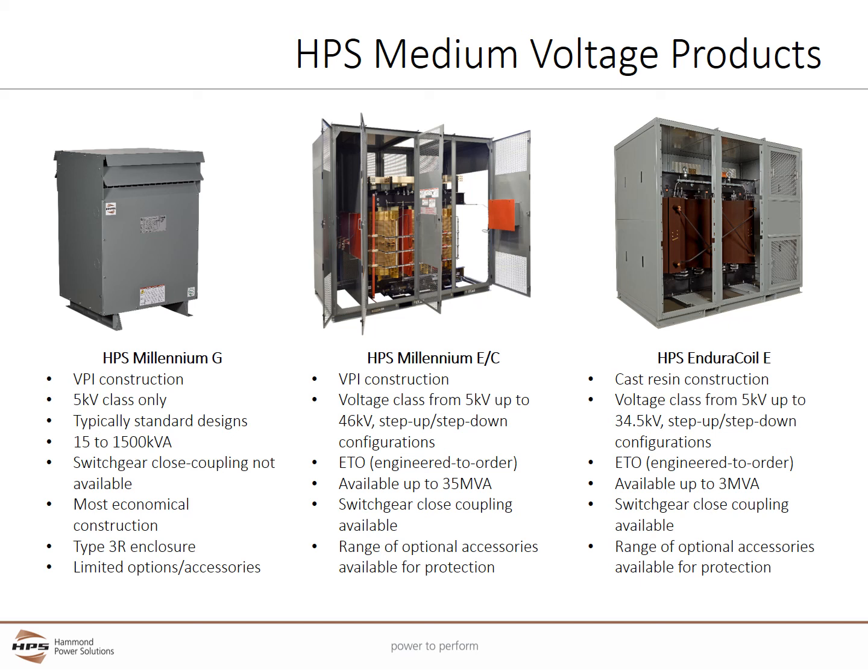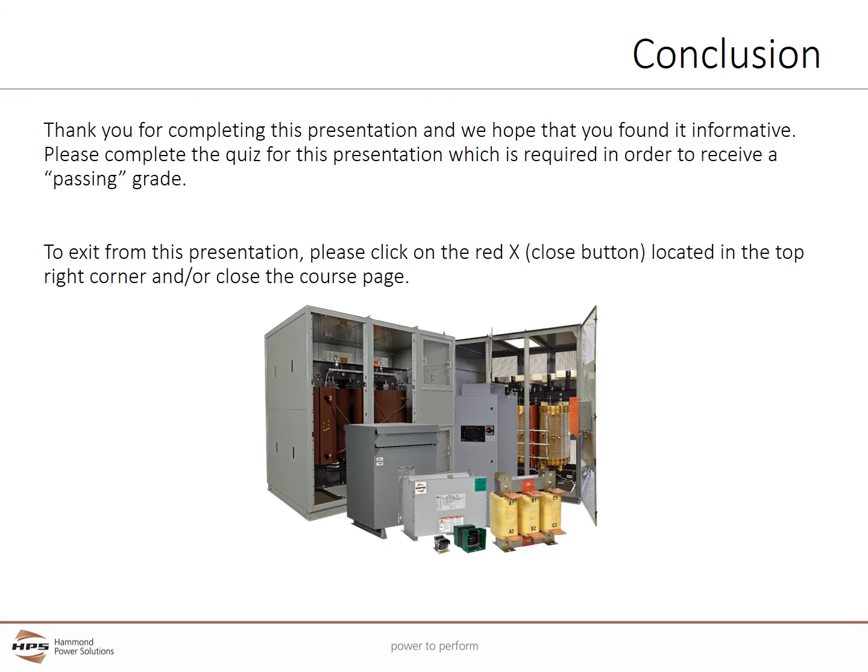The HPS EnduraCoil E uses cast coil construction. It offers voltage classes from 5kV up to 34.5kV in step up or step down configurations. It is engineered to order and available up to 3 MVA. The EnduraCoil can be close coupled to switchgear and provides a broad range of optional accessories available for customization and protection. Thank you for completing this presentation. We hope you have found it informative.